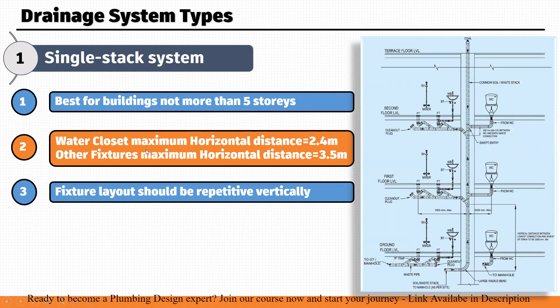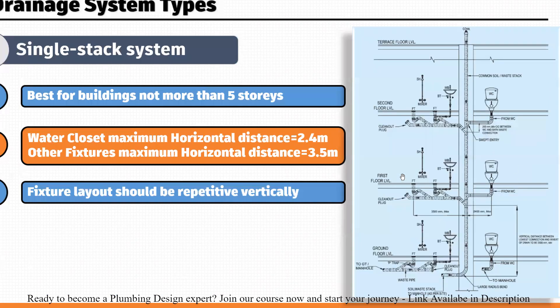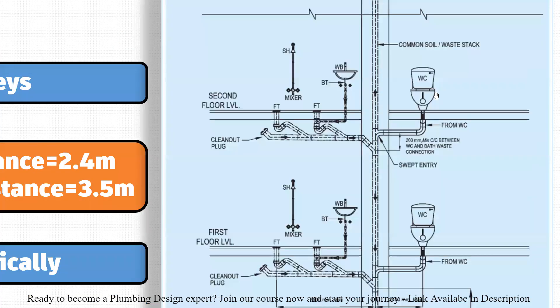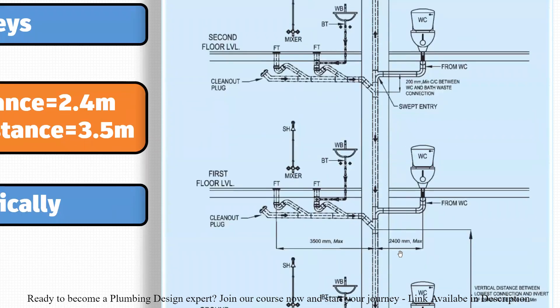The second point concerns the water closet maximum horizontal distance. If you are connecting a water closet to this vertical pipe, the horizontal distance between the WC and the pipe should not be more than 2,400 mm — it must be less than 2,400 mm.